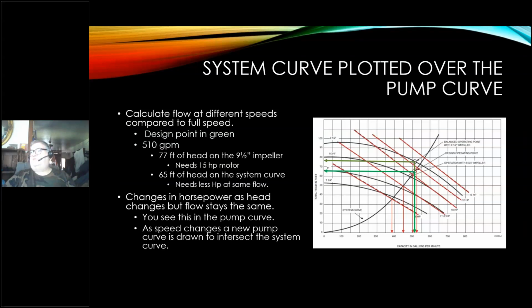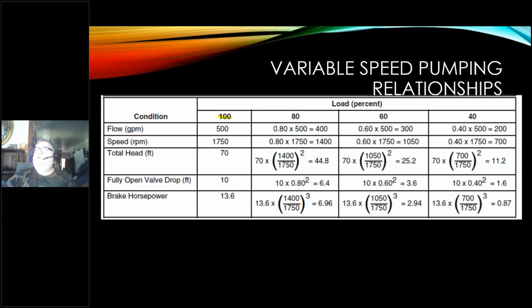As the speed changes, the new pump curve is drawn to intersect the system curve. So you had the pump curve, now you plotted your system curve against that, and now you see a different point of performance at that design flow. Again, the pump is designed out of the factory, but once it's installed in the field, things change. And so that's where the system curve comes in. Again, here's an example using different flows.